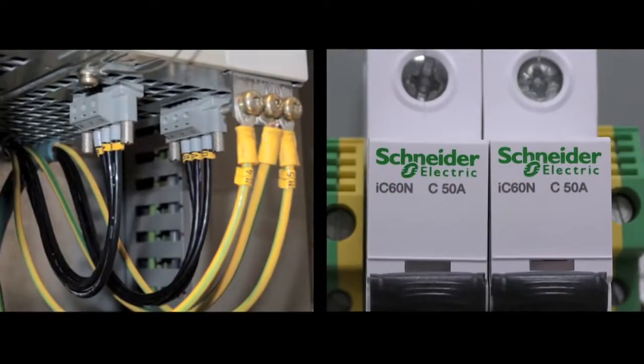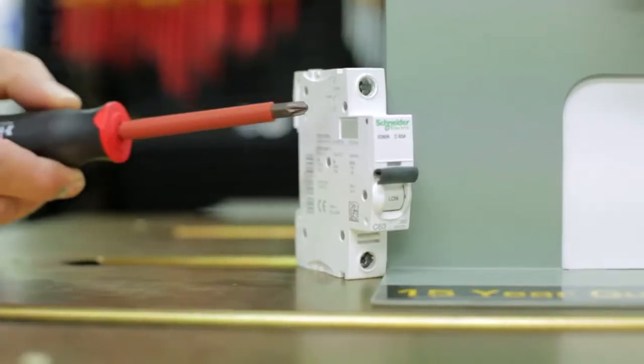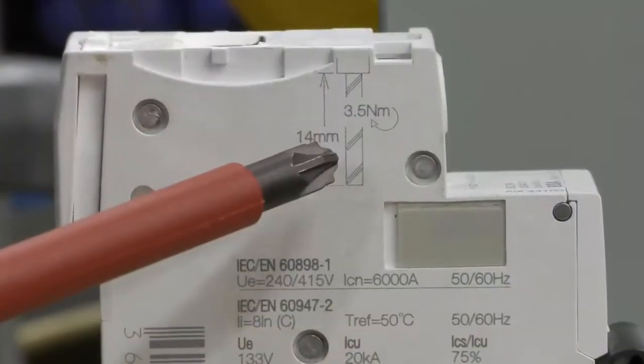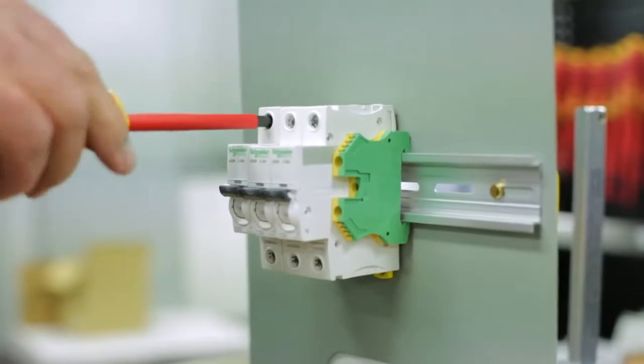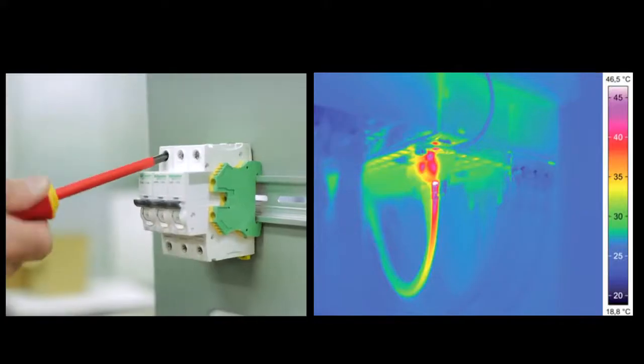Switchboard cabinets and machines are increasingly equipped with screws made of copper, aluminium and plastics. Over-torquing will damage screw and thread and prevent the connection from being safe. Under or over-torquing may result in heat build-up.